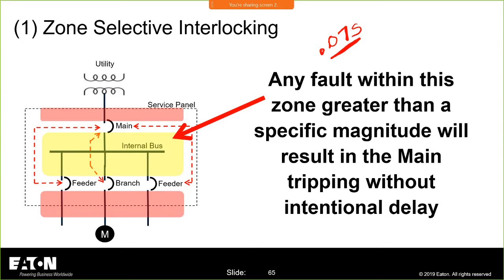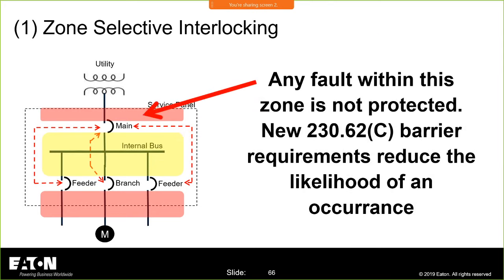So then the panel said, you know what, you're right. We can't hold one to a higher standard. So that is where the 0.07 seconds came from, because your typical clearing times for ZSI, zone selective interlocking, are 0.07 seconds. And that's all I have to say about that. That's where that came from. You don't get any protection outside of those zones of protection of things.